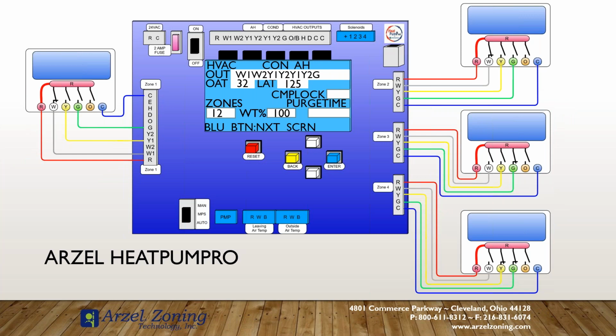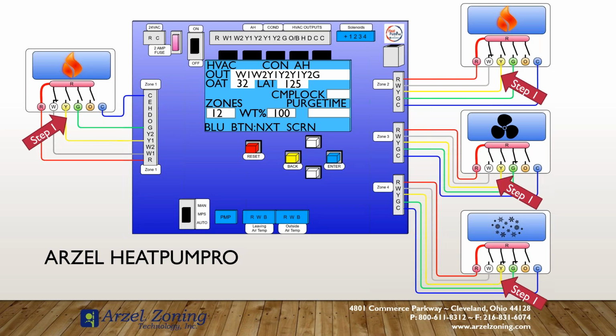So when we start looking at how things are calling, I'm not sure if my slide reset or if it doubled up. We start at our thermostats, step 1. We verify that our thermostats are calling. From there, we move to the zone panel itself. We verify that the zone panel is receiving those calls. And then once we verify the zone panel is receiving the calls, we can verify the HVAC outputs.